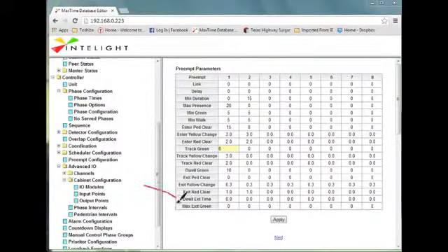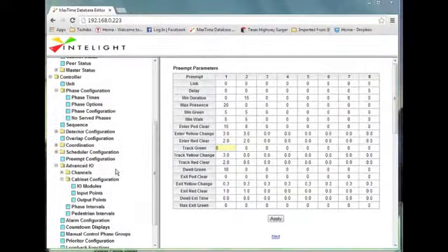The next value we have is the dwell extension timer. What we're doing here is we have a value to use like a gap out or extension time. If we have a flickering detector, like some infrared type devices may give us a flicker, we want to make sure that the detector's gone away completely before we exit out of preempt. So that's what this is.